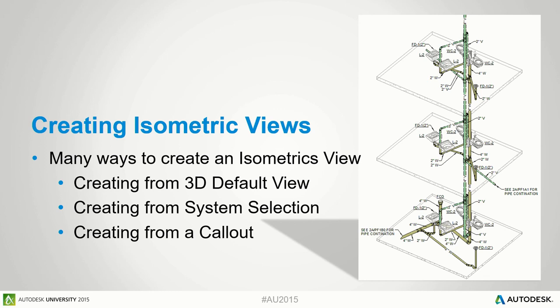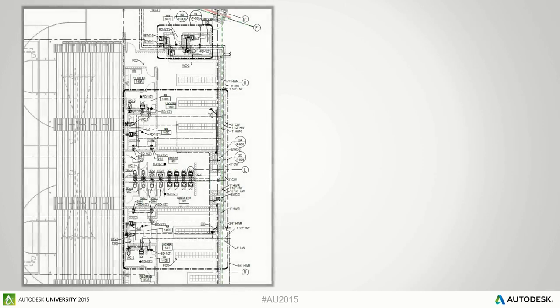The one we see most is creating ISOs from callouts. What it allows us to do is create ISOs that are location-specific rather than just system-specific. When areas get very congested, we create a callout on that area on the plan and do an ISO of that callout, which allows us to make a direct reference in our construction documents and sheets from the plan directly to the ISO placed on another sheet.